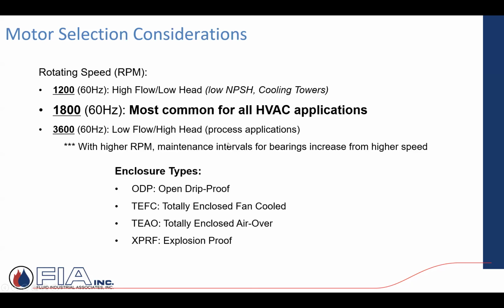With the higher RPMs, there are maintenance intervals, et cetera, bearings, higher speed, higher temperature. A couple of different enclosure types: ODP, TEFC (totally enclosed, fan cooled), air over, not that common, and then explosion proof. Those are the different types of enclosures for the motor itself that you're going to see out in the field.